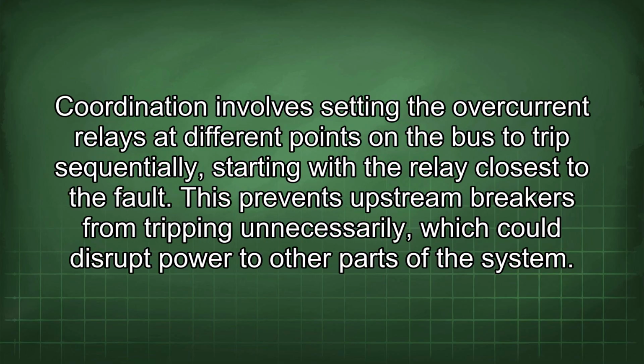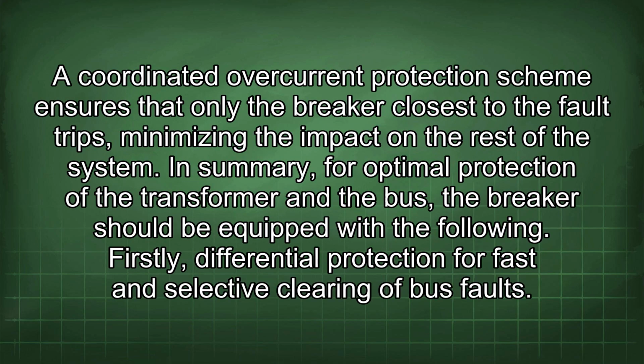Coordination involves setting the overcurrent relays at different points on the bus to trip sequentially, starting with the relay closest to the fault. This prevents upstream breakers from tripping unnecessarily, which could disrupt power to other parts of the system. A coordinated overcurrent protection scheme ensures that only the breaker closest to a fault trips, minimizing the impact on the rest of the system.